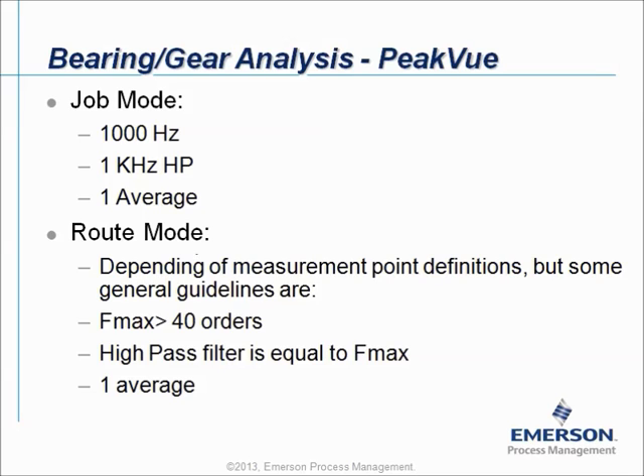If you collect PeakVue data starting from the route mode, it will depend on the measurement point definitions, but here are a couple of general guidelines. It is recommended to use an Fmax of at least 40 orders or higher, and the high pass filter is normally more or less equal to the Fmax. So if your Fmax is 1000 Hz, the high pass filter will be 1000 Hz; if the Fmax is 2000 Hz, the high pass filter will be 2000 Hz. In PeakVue measurements, very importantly, we always collect only one average.